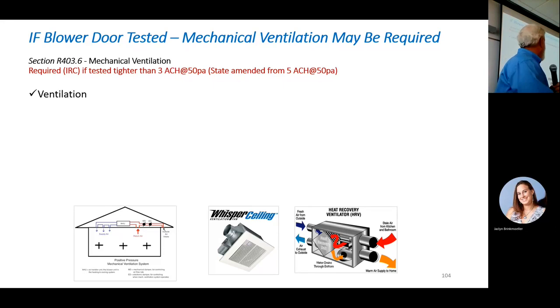The code allows you to do that. So you bring in some air, you positive pressure, and you let it leak out. It complies. The next one is we put a fan, or maybe we do 2 fans that run all the time. And Panasonic makes their Whisper series fan or Whisper Green, and they have a number of different fans. And they are very, very efficient fans. In fact, their current draw on them is similar to the current draw on a doorbell transformer. So it's very, very low. You cannot hear them running. I don't know how many of you have ever put in a Panasonic fan or seen one. You could have been in projects that had them and you wouldn't know it because you can't hear them running.